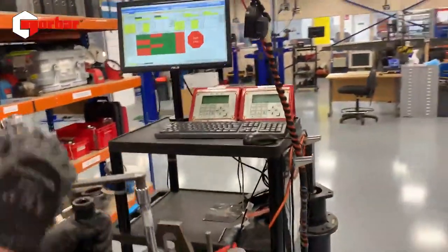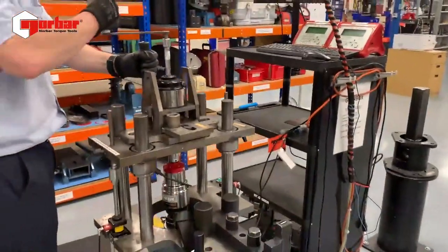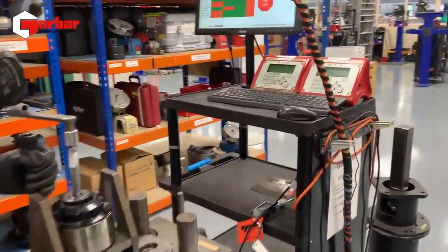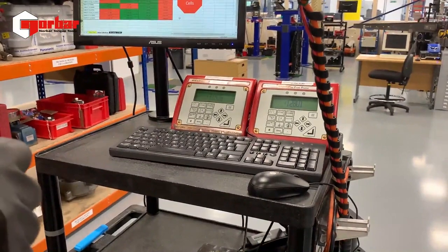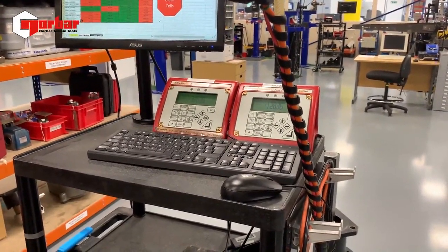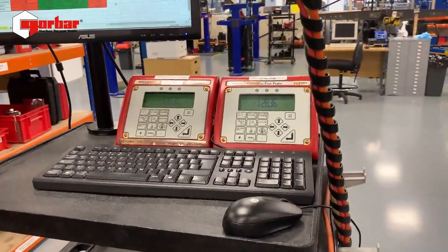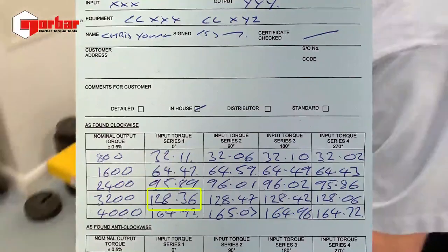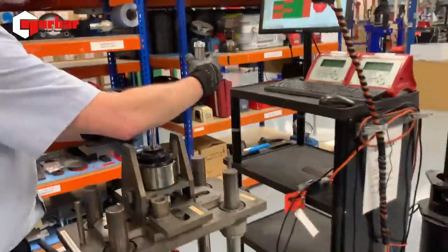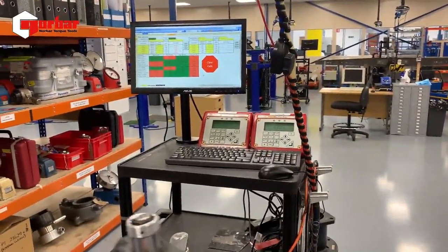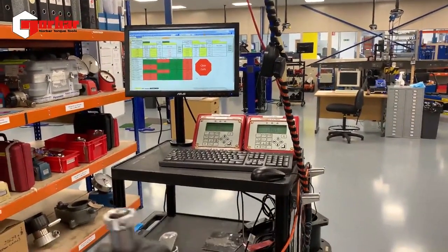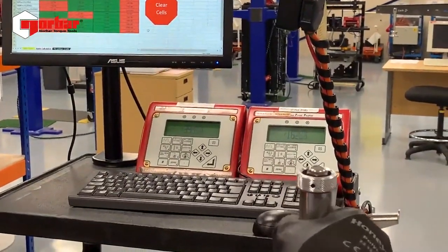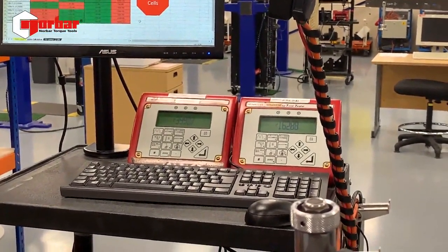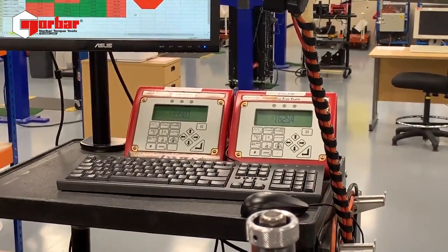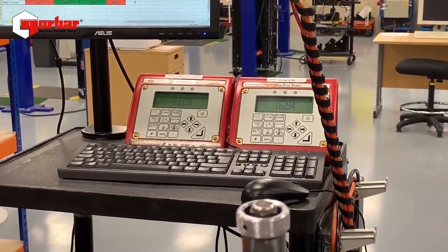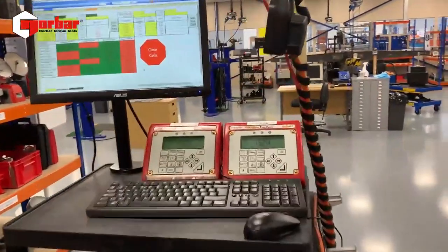Okay. We're now going to 80% of full scale, which is 3,200 Newton meters. Again, small amount of overshoot there, but the figure I'm capturing is 128.36. We're now going to full scale and our final reading. Okay, so 4,000.6 on the output, 162.94 on the input.